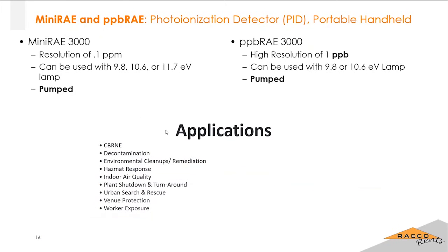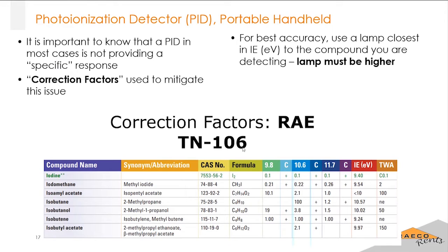Here's one of them, RAE Technical Note 106. It shows you the compound name and tells you what the IE is, with electron volts in parentheses. For example, an 11.7 lamp is considered 11.7 electron volts, and these go hand in hand. For the highest accuracy, you want to use a lamp closest in ionization energy to the compound you're detecting, and at the very least, the lamp should be higher than that. Iodine, for instance, has a 9.4 IE, so the 9.8 lamp would probably be the most accurate for it.